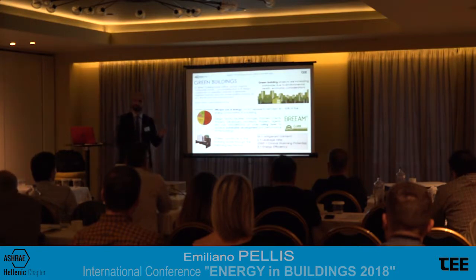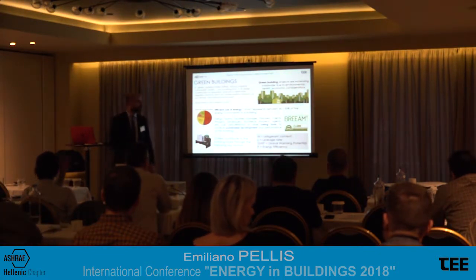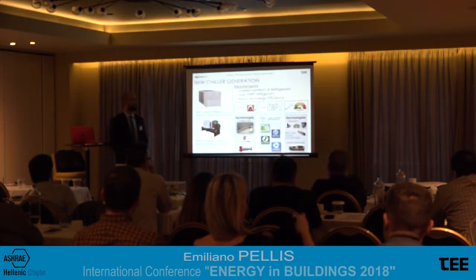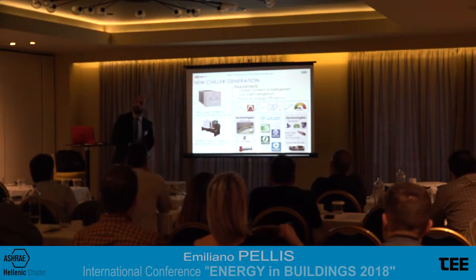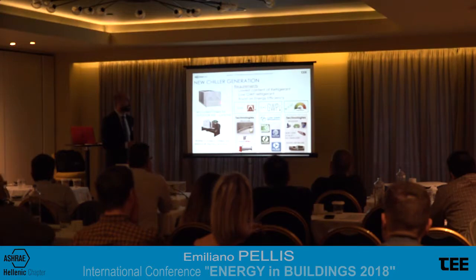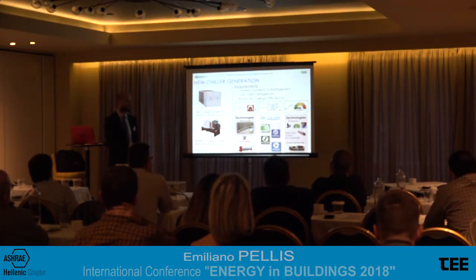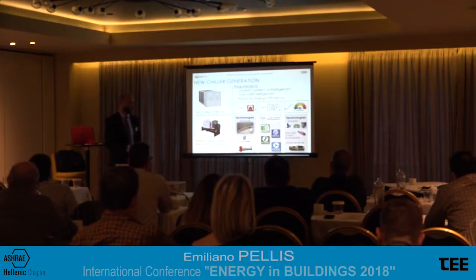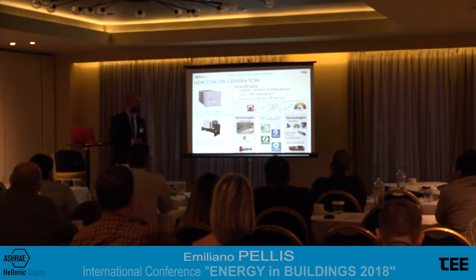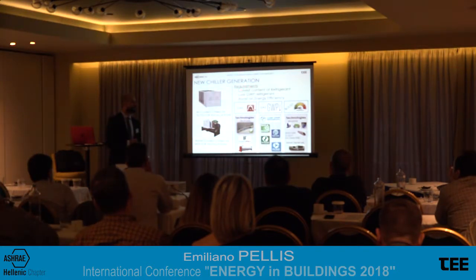There are also other parameters, for example, related to the possibility to recycle the materials, but for sure these 4 factors are very important. So, taking into account this, what are in the end the technical requirements for the new generation of chillers, both air-cooled, so intended for outdoor installation, or water-cooled, so intended for indoor installation, so in a technical room? The requirements are the future chiller will need to have the lowest content of refrigerant, the lowest GWP refrigerant, and a boost in terms of energy efficiency.